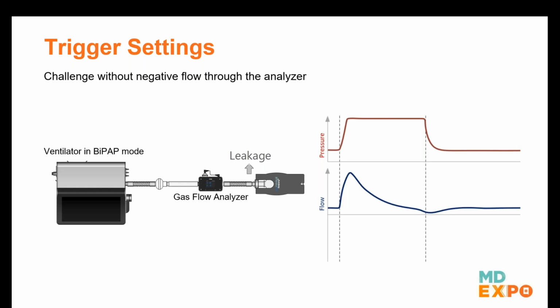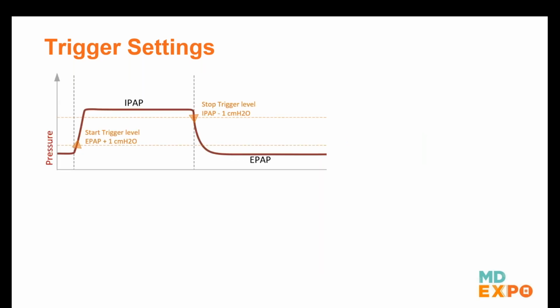On the other hand, the pressure signal looks good here, right? We have steep edges, so we can use the pressure signal. As we have learned earlier, we can select in the gas flow analyzer whether we want to use the flow or pressure signal to trigger. So in this case, we could trigger on the pressure signal. The upper pressure level in BiPAP is called IPAP, and the lower level is called EPAP. In such a situation, we would typically set the start trigger on a rising edge at EPAP plus 1 centimeter of water pressure, and then the stop trigger on a falling edge at IPAP minus 1 centimeter of water pressure. That allows us to trigger in this specific application.